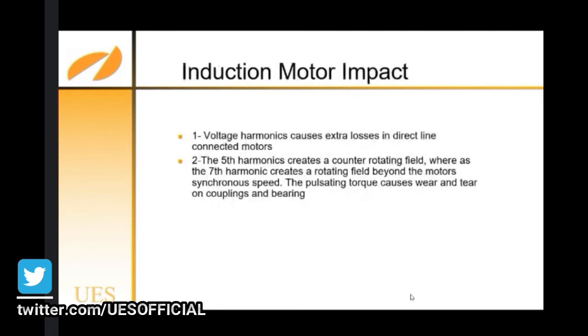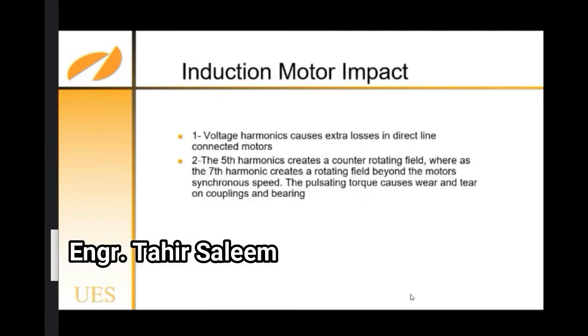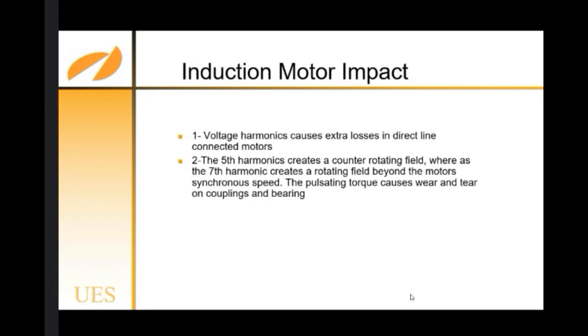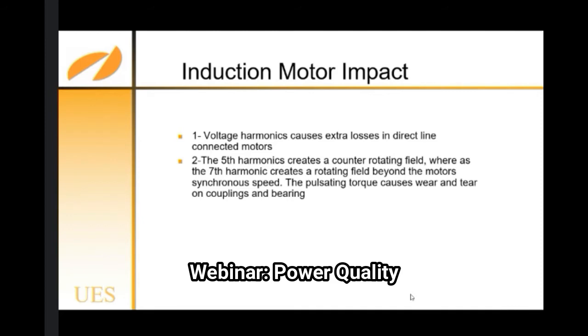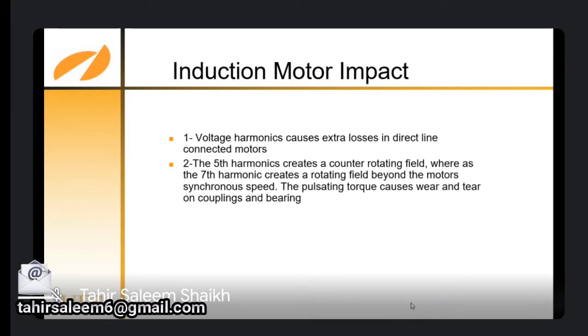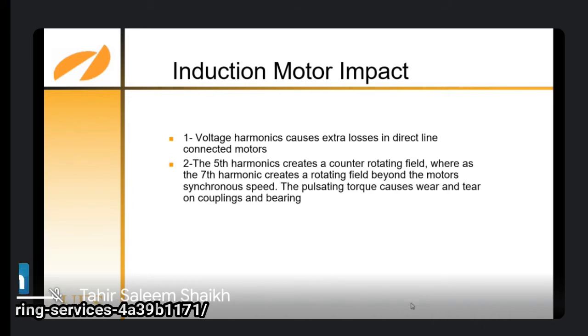Next, motor impact: voltage harmonics cause extra losses in direct line connected motors. The fifth harmonic creates a counter rotating field, whereas the seventh harmonic creates a rotating field, pushing the motor toward synchronous speed. The pulsating torque causes wear and tear on couplings and bearings. Normally, the use of VFDs creates fifth and seventh harmonics. UPS create a third harmonic. Third harmonic means three times the base frequency, if you are using a 50 Hz base frequency, and the fifth harmonic means 250 Hz. They interfere with the main supply voltage. The fifth and seventh harmonics damage the motor bearings.